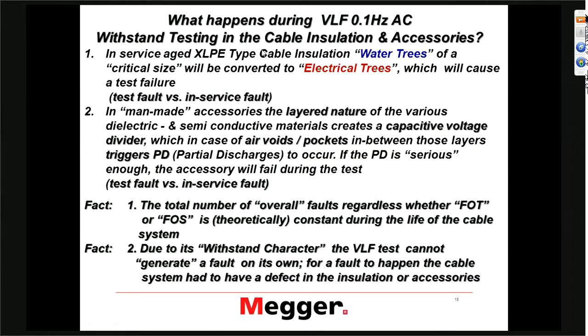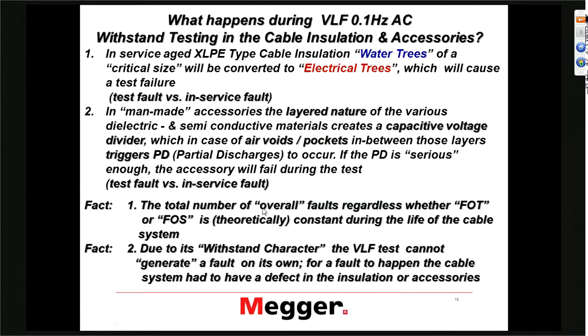When you put the VLF voltage on and reach that critical voltage in the splice or termination, you might get a splice failure during that test. The fact is, the total number of overall faults — regardless of whether you test or don't test — is theoretically the same. The question is: when do you see these faults? Do you show them as failures in service, or as failures on test?